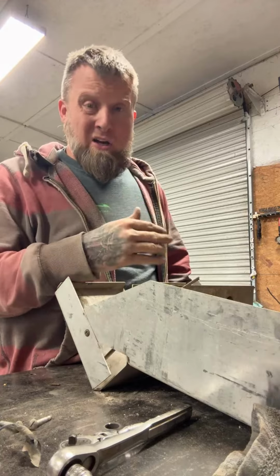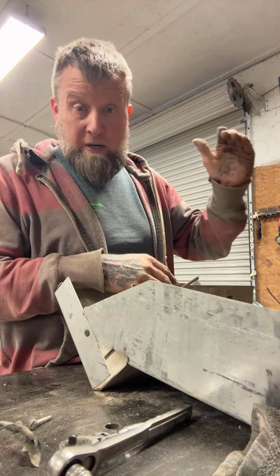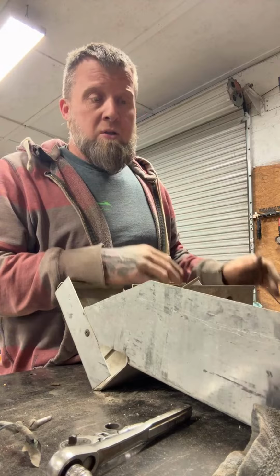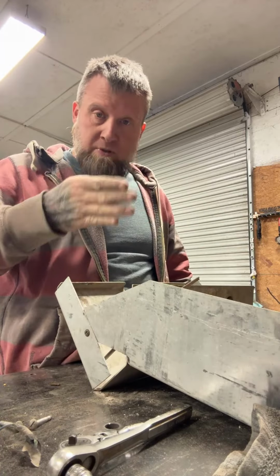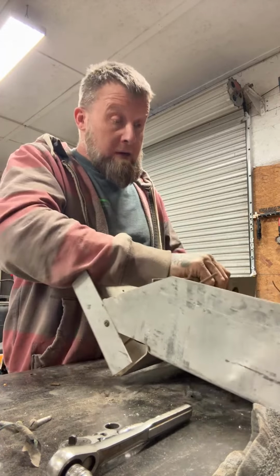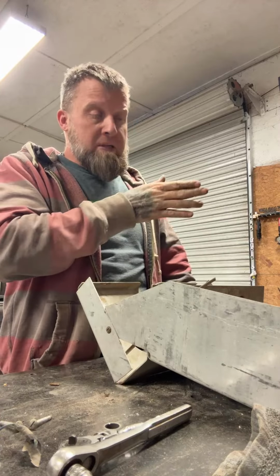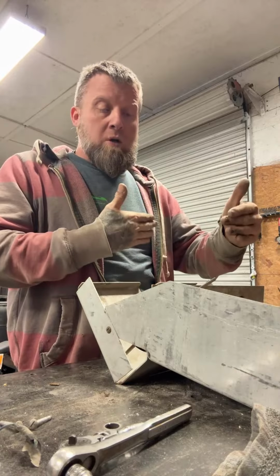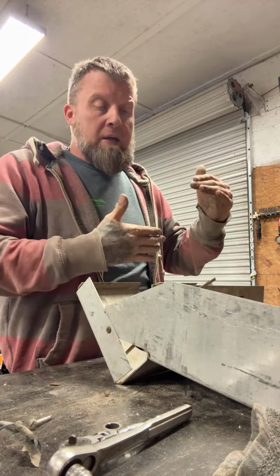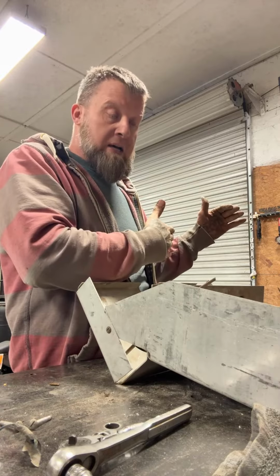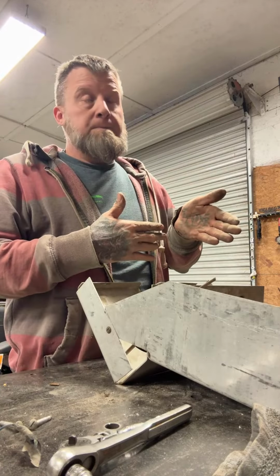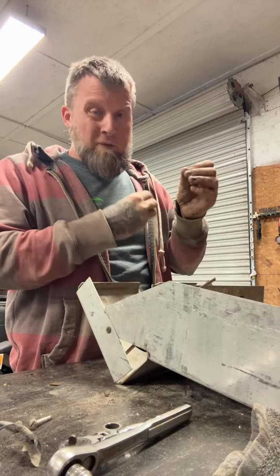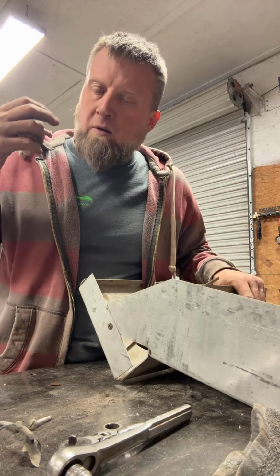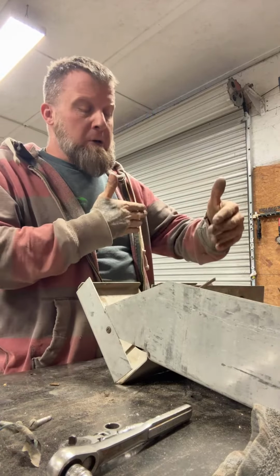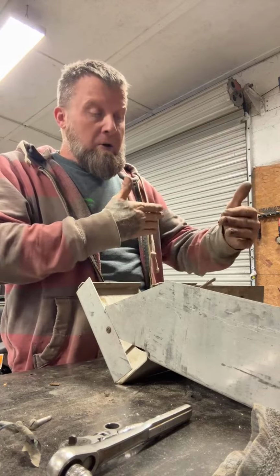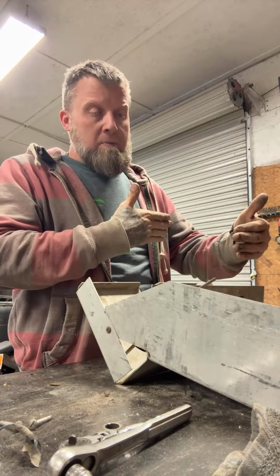If it runs for a while and doesn't achieve that temperature, your heat strips come on. Most systems have 3 or 4 heat strips, and they pull a lot of power, kilowatts. The first heat strip will come on when the timer senses we're not getting enough heat from the compressor side. It runs for a little bit, and that's when you smell that dust burning smell, because it's burning off the dust in the air. Once that first heat strip comes on, it starts warming the air up.